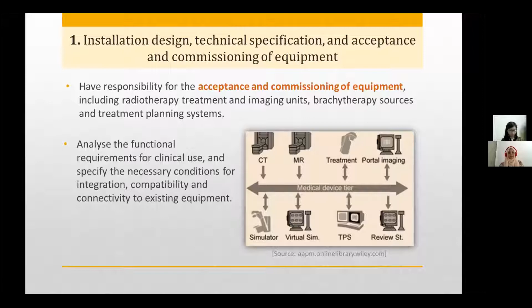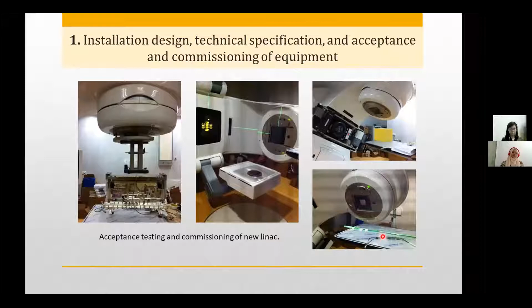So this is our new LINAC machine installed about 5 years ago. We have done some tests during the acceptance testing and commissioning. For example, this is the test for electron beam using the water phantom prepared by the vendor. And then this one is to test the image quality for OBI. This is to test the collision. And then we test for the photon beam as well.